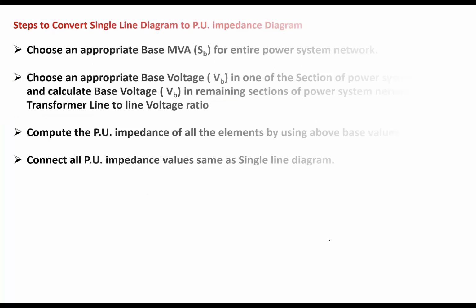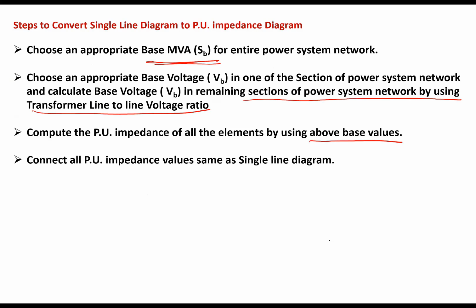So the first step is, in the problem he will give the base MVA for the power system network, and he will also give the base voltage for one of the sections. So you have to calculate base voltages in other sections. Then depending upon the base MVA and base voltage of the element in that section, you have to calculate the per unit impedances of all the elements and connect all the per unit impedances in the form of a single line diagram. So that is how you convert the single line diagram into per unit impedance diagram.